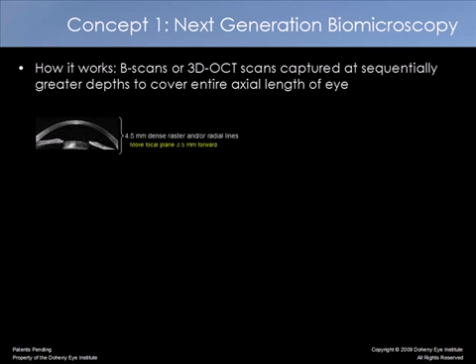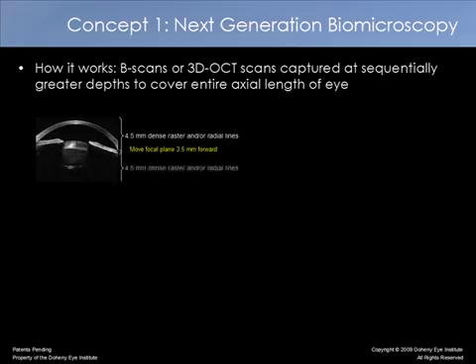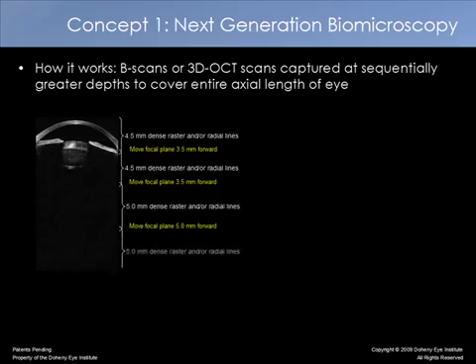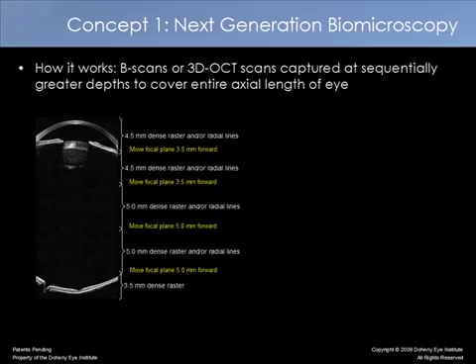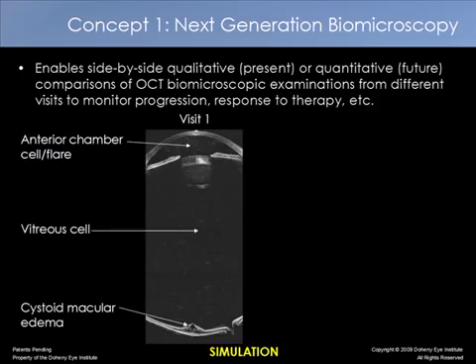How would it work? B-scans or 3D OCT scans could be captured sequentially at greater depths each time to cover the entire axis of the eye. What you see here is a scan of the anterior segment. The machine moves the focal plane back a few millimeters, scans the lens, moves back a few millimeters, scans the vitreous, and so on, until the machine has moved the focal point all the way back to the retina and choroid, capturing sequentially an entire set of B-scans for the eye.